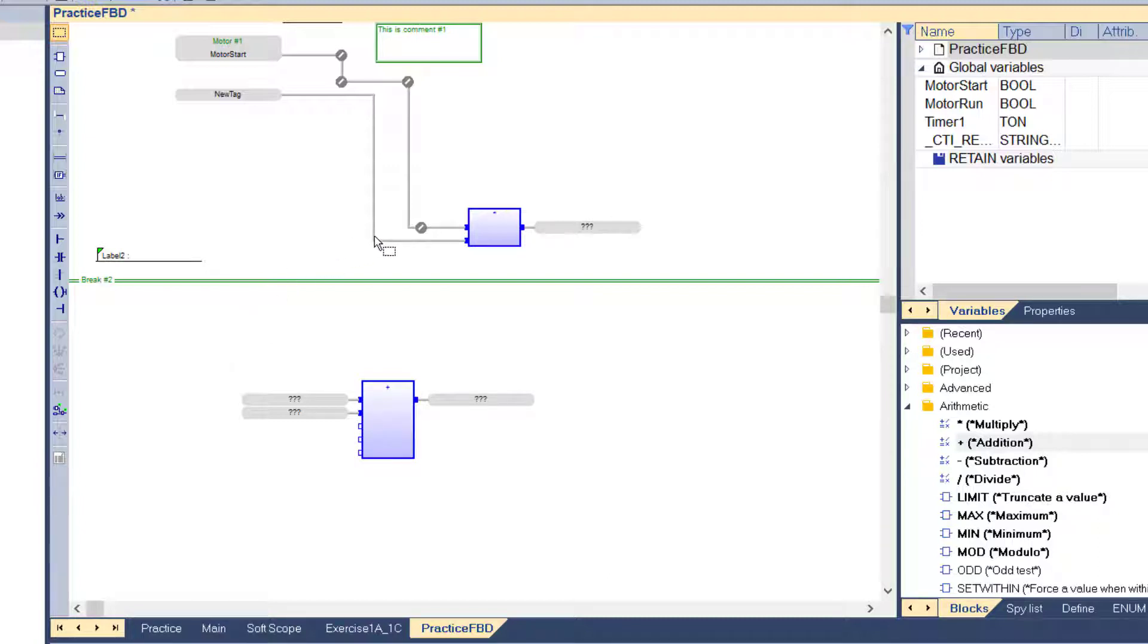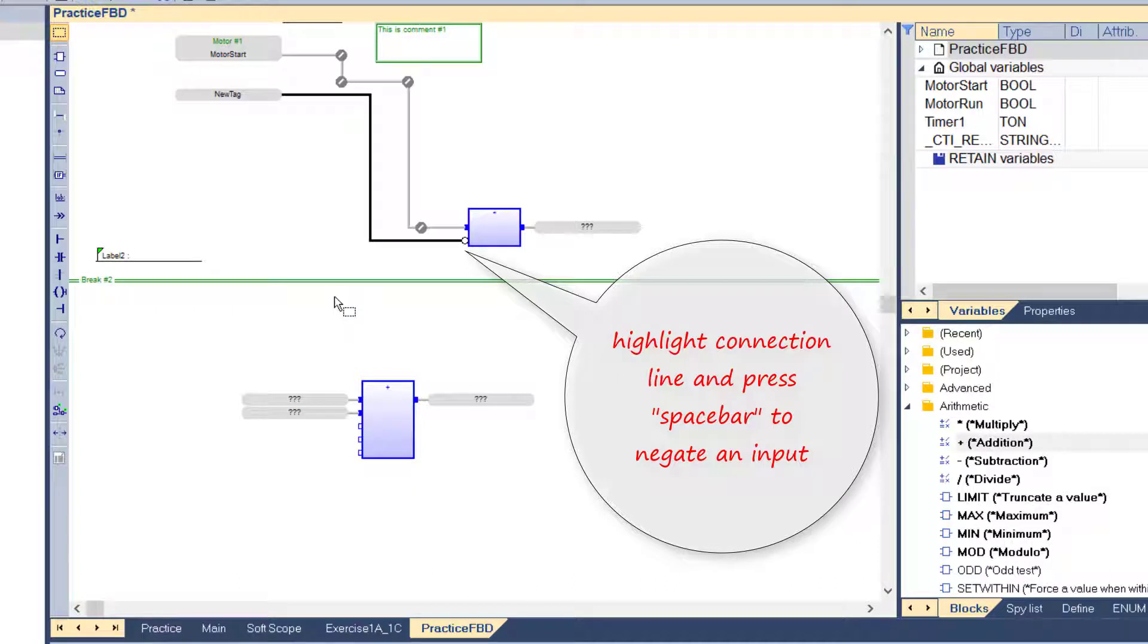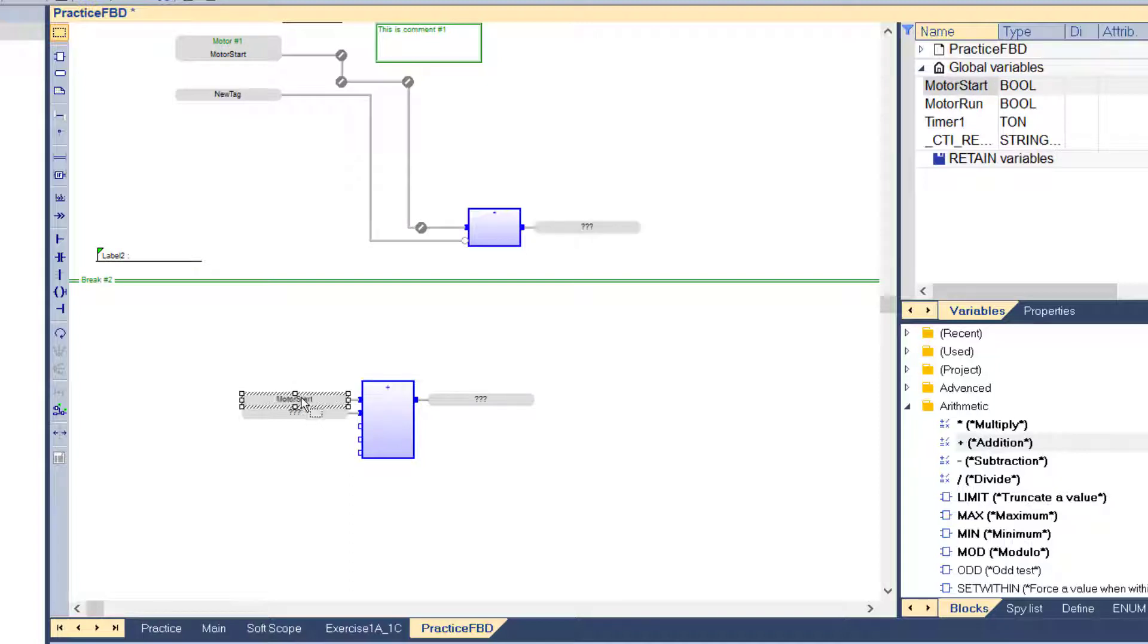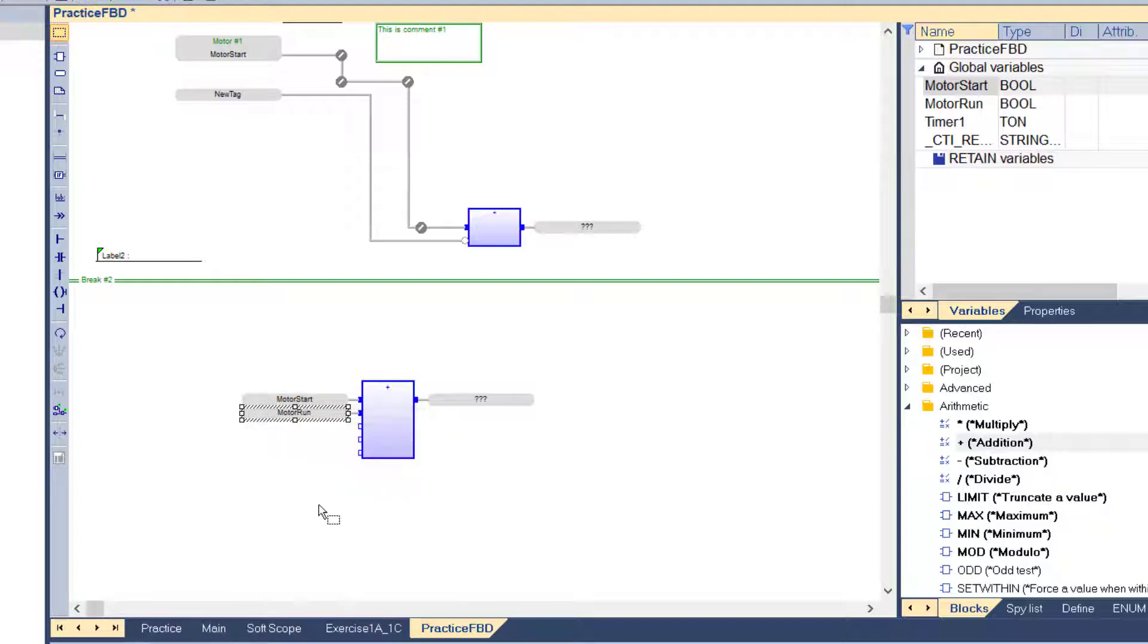Inputs to function blocks can be negated by highlighting the connection line and pressing the space bar. To insert a variable, you can simply drag it from the variables pane to the variable box where you want to attach it. Alternately you can double-click on a variable box to bring up the variable editing dialog.